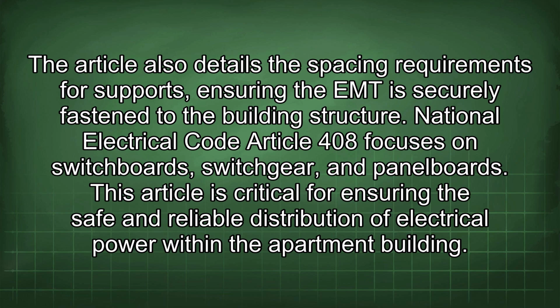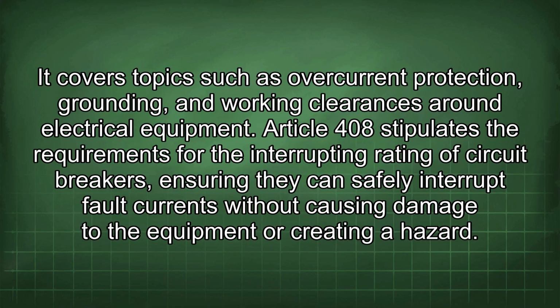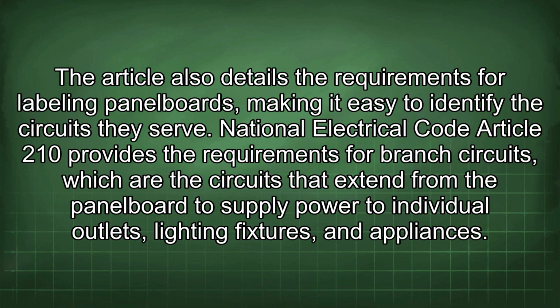National Electrical Code Article 408 focuses on switchboards, switchgear, and panel boards. This article is critical for ensuring the safe and reliable distribution of electrical power within the apartment building. It covers topics such as overcurrent protection, grounding, and working clearances around electrical equipment. Article 408 stipulates the requirements for the interrupting rating of circuit breakers, ensuring they can safely interrupt fault currents without causing damage to the equipment or creating a hazard. The article also details the requirements for labeling panel boards, making it easy to identify the circuits they serve.